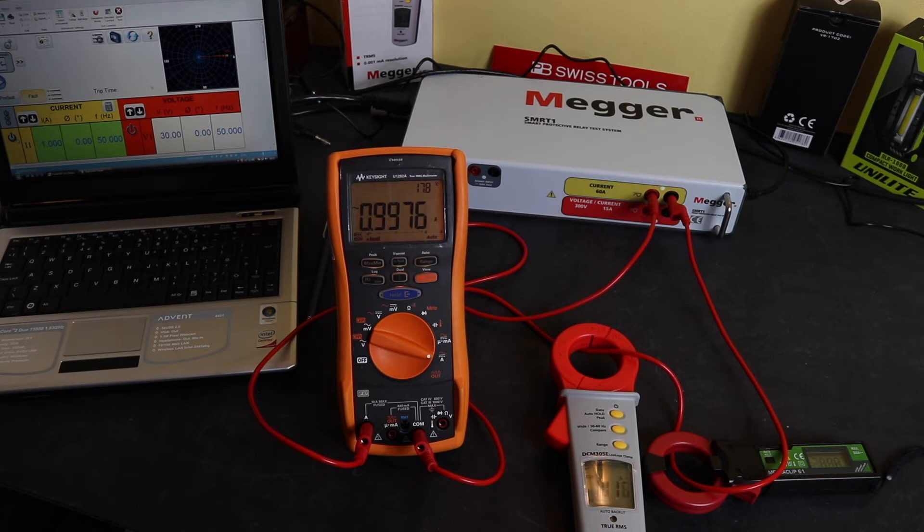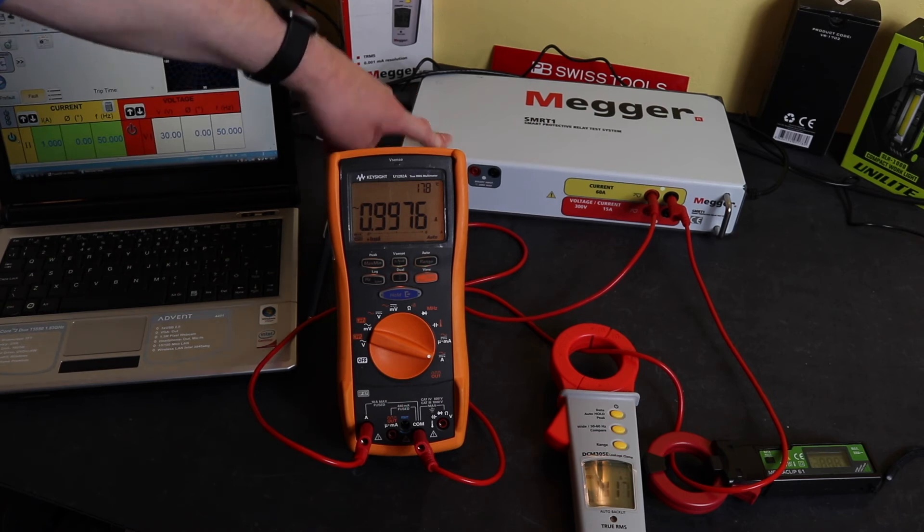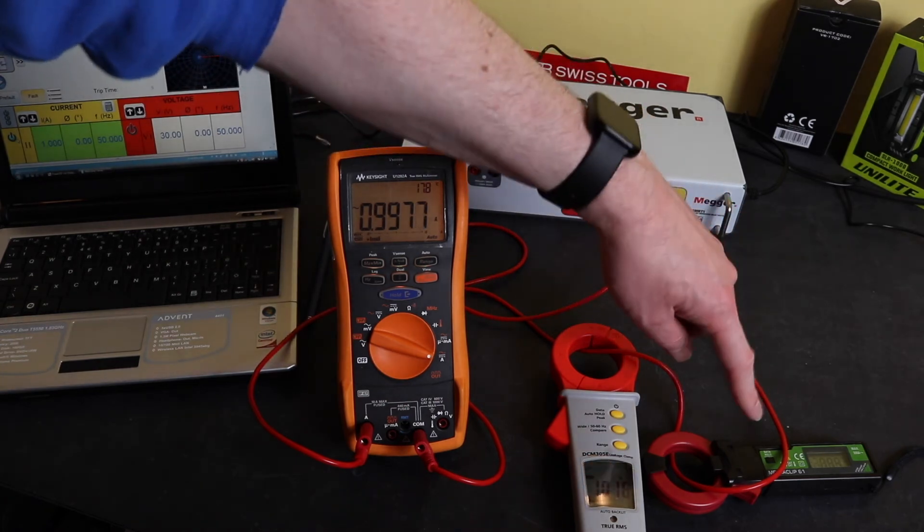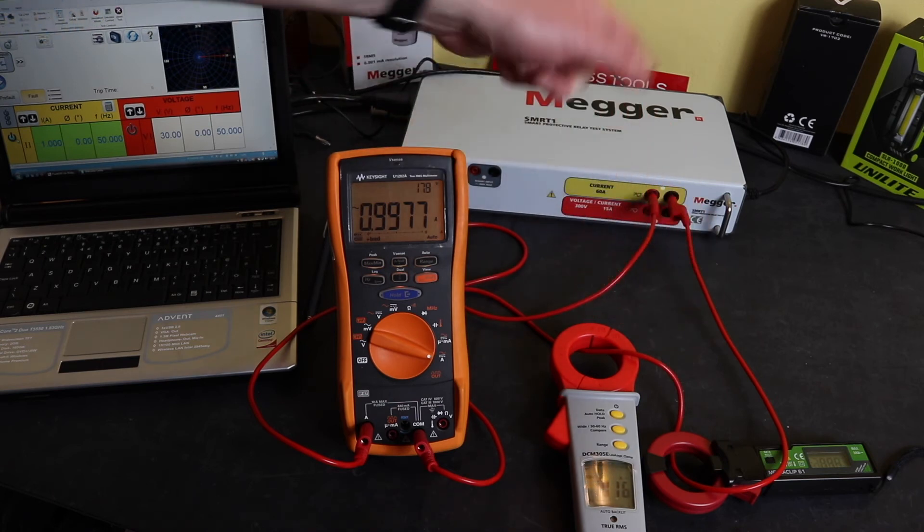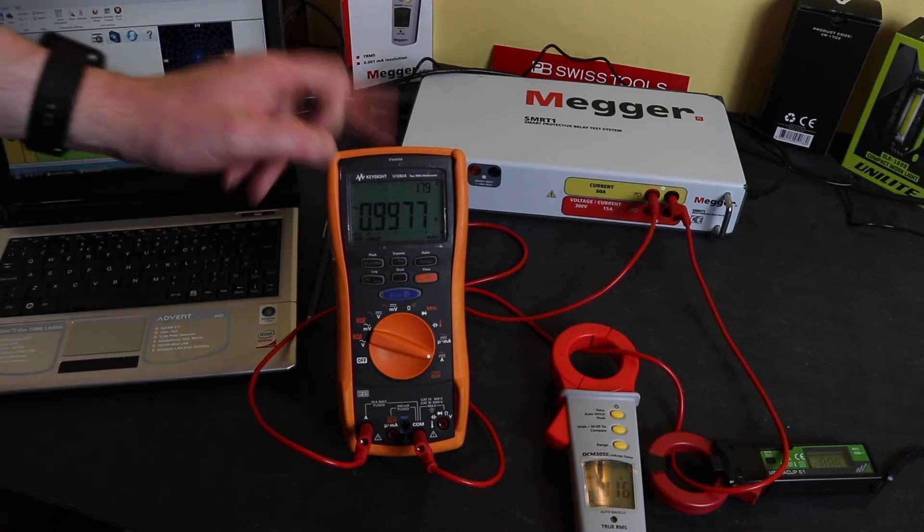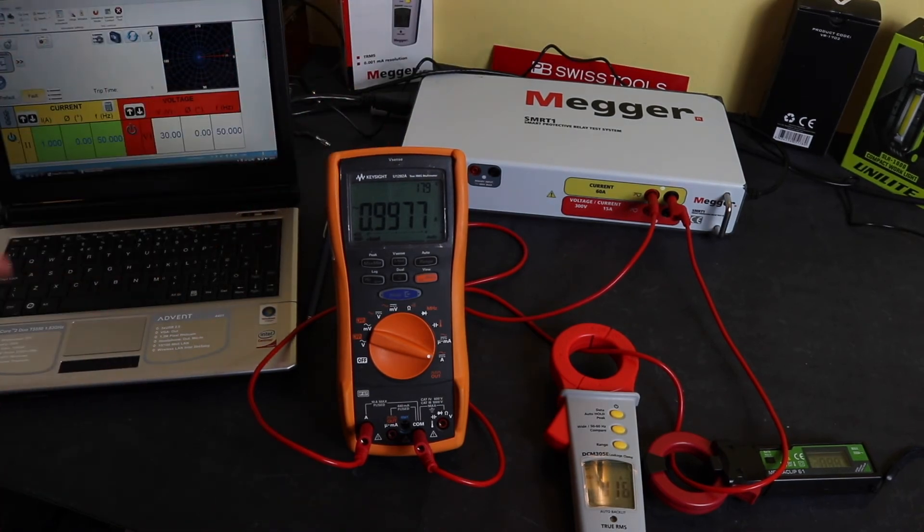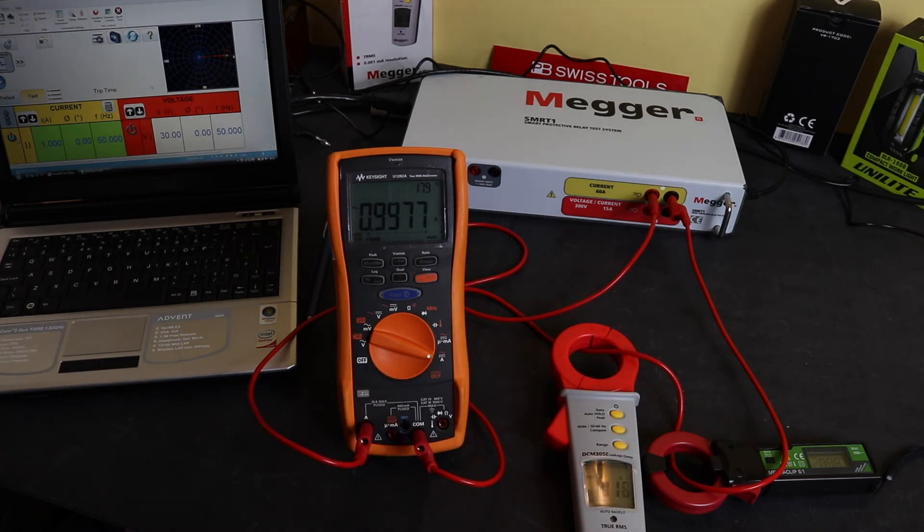So this is the test setup for 10 amps down to around about 100 milliamps. I'm still using the SMRT in current mode. I've got a lead coming straight out going through both the current clamps through an ammeter and then back into the test set. I'm just using the ammeter as a cross reference for the current that I'm putting in which is 1 amp at the moment and we're 0.9977, 1.016 on Megger and 0.96 bouncing around a bit on the Metrawatt there. So I'll use this test setup now until we get down to the really low milliamps.